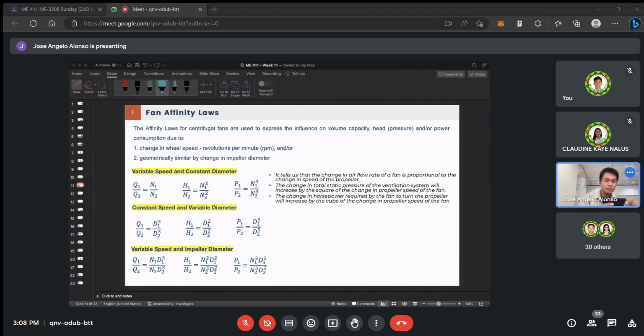Check ko lang na. Well, general assumption lang naman to. Correct, so nasa 44% yung magiging increase ng ating total head kapag ang rotational speed ay increased by 20%. Wherein the change in horsepower required by the fan to turn the propeller will increase by the cube of the change in the propeller speed of the fan.